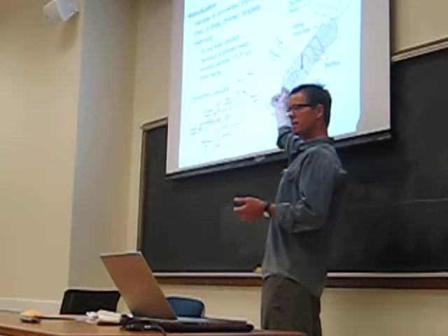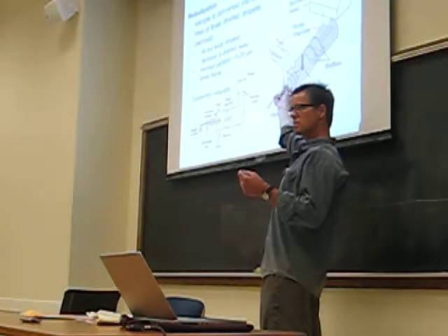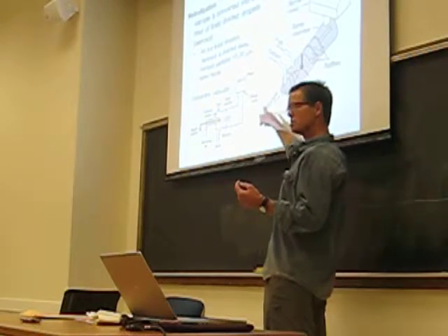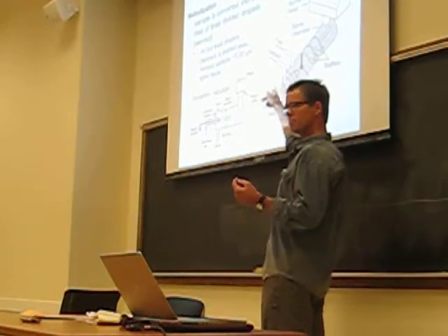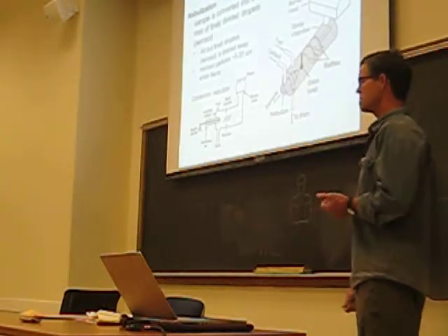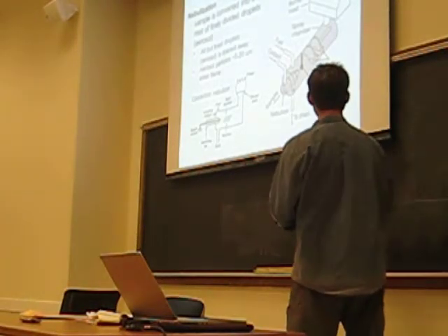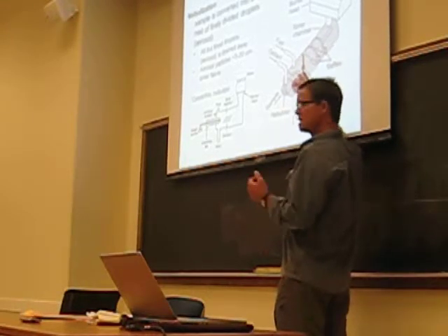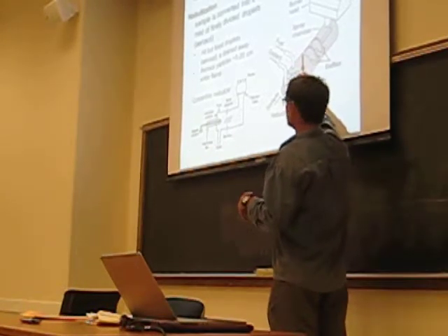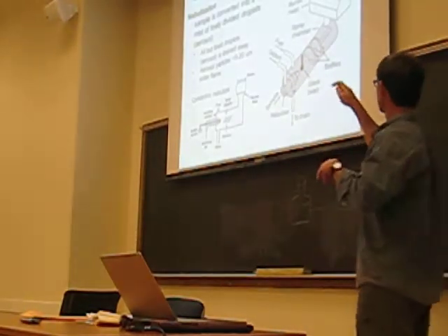So you see the capillary tube. You know you can adjust a little knob right here that essentially opens and closes the orifice diameter. It essentially allows it to aspirate more or less sample liquid. And the aspiration rate, so you can change that. Okay. The sample goes in, in this example with this one, it hits this glass bead, like you said, and it generates this mist of droplets, liquid droplets.